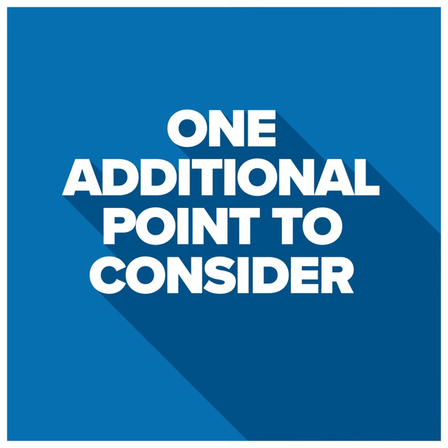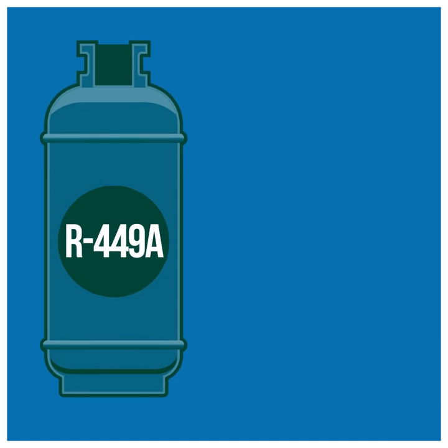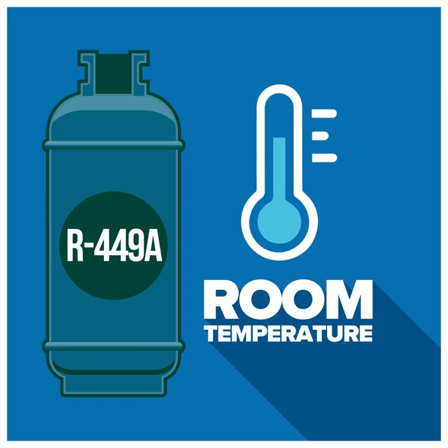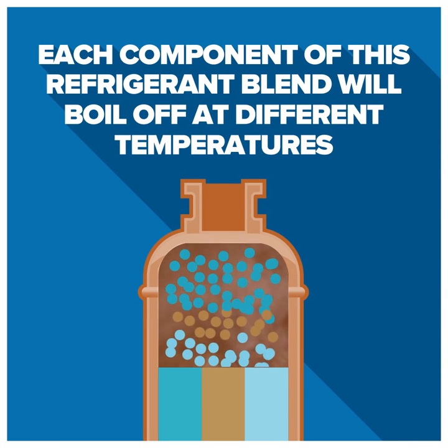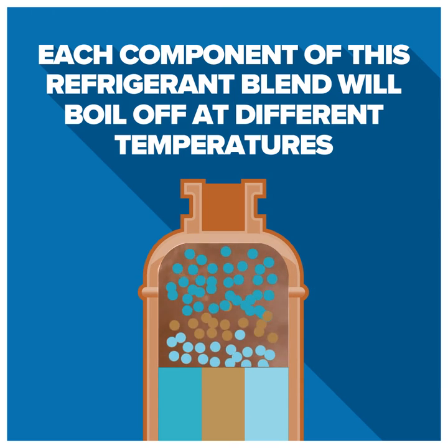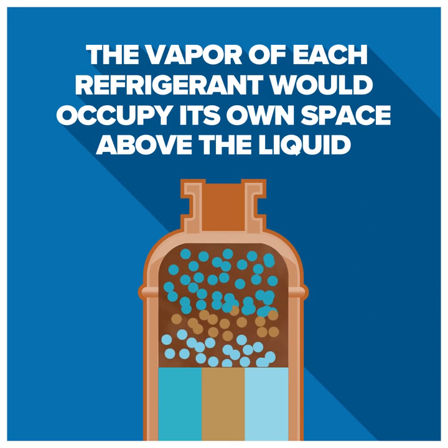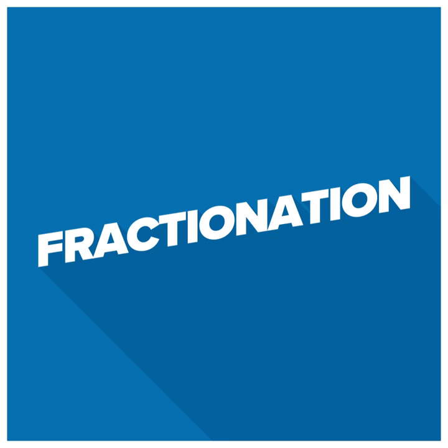In this connection, there is one additional point to consider, and this is fractionation. Let's continue using R449A, and let's say the bottle is stored at room temperature. Each component of this refrigerant blend will boil off at a different temperature, separating from the liquid mixture. The vapour of each refrigerant would occupy its own space above the liquid. This is known as fractionation.